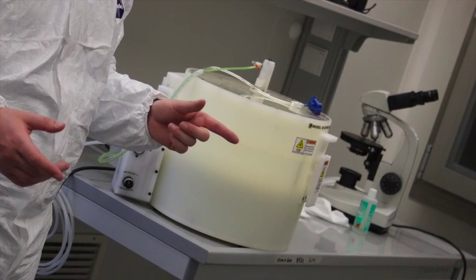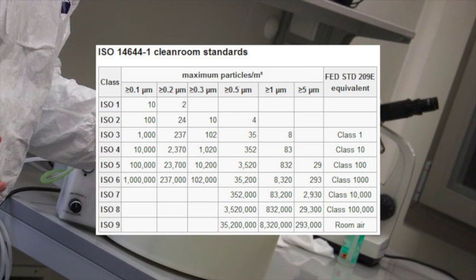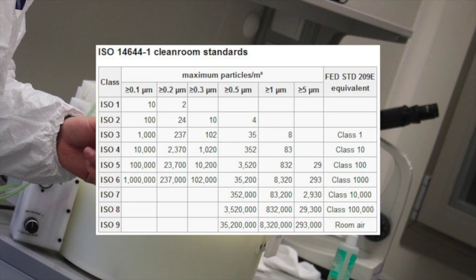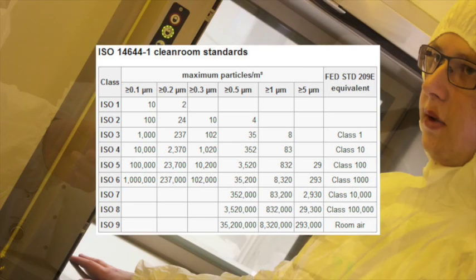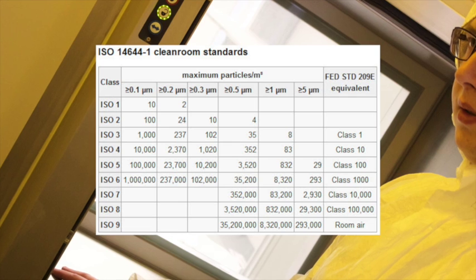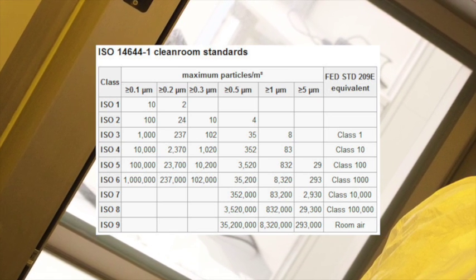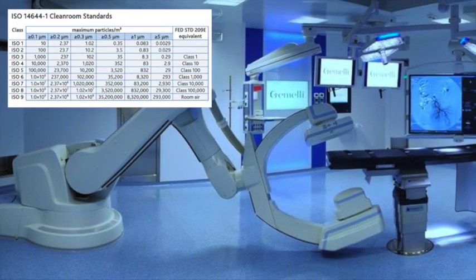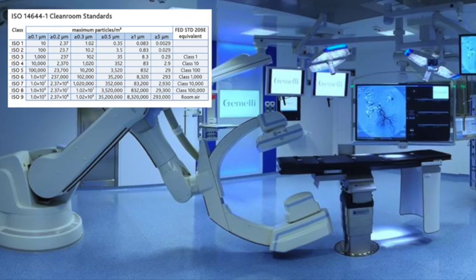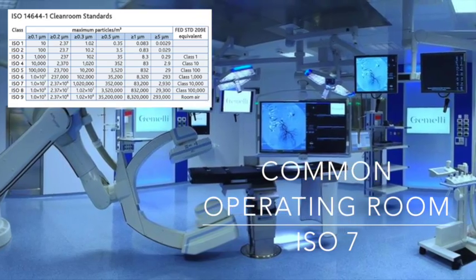The ISO 14644 standard establishes a classification of clean rooms depending on the number and size of particles per cubic meter. Prior to ISO 14644, technicians used the FED STD-209E standard. Although this standard is no longer supported, its classification is still very popular. To get an idea of cleanliness, a typical clean room for ISO 3 integrated circuit manufacturing is far cleaner than a hospital operating room, which would be classified as ISO 7.